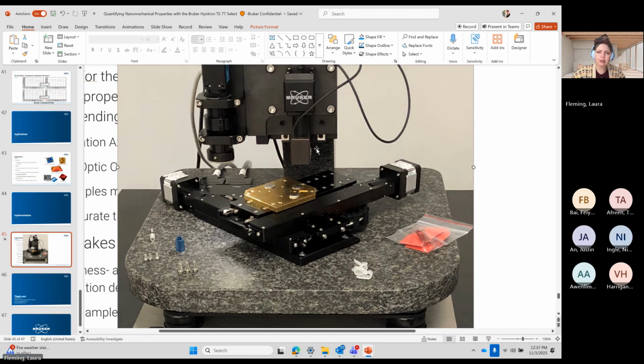I also recommend that you always slide the transducer fully onto the piezo scanner, meaning there is a sidewall here. So this side is open. This side has a stop. So slide left to right, and then hold your finger against the transducer as you tighten it so it doesn't jump away. Doing so will make some of the calibrations easier. It's not the end of the world if you don't, but it should be as far on that piezo scanner as possible.